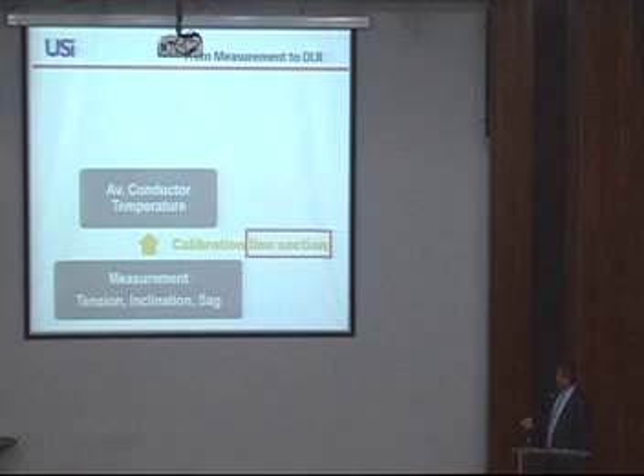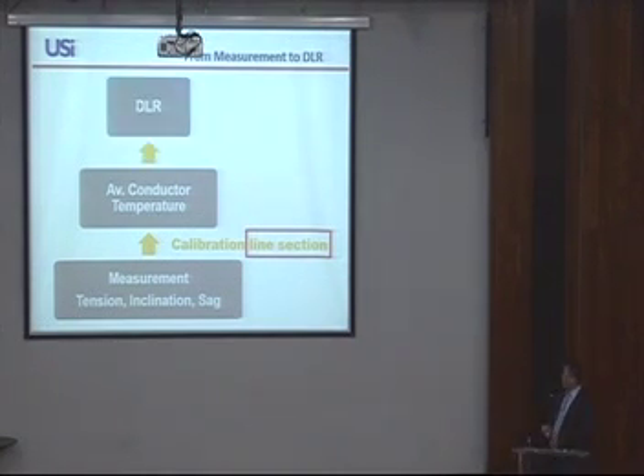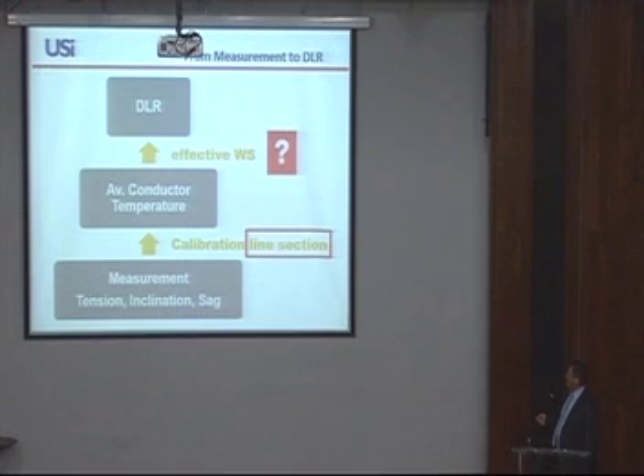So now the next step, because the average temperature doesn't tell a lot to the operator. The operator does not work with temperatures, he needs currents. So we have to get from the conductor temperature to the thermal capacity of a line. And this requires another step in between, which I will not explain in detail, but you have to determine the effective wind speed, or one effective wind speed, I would say. You can find more about this definition and how to do that in the brochures.